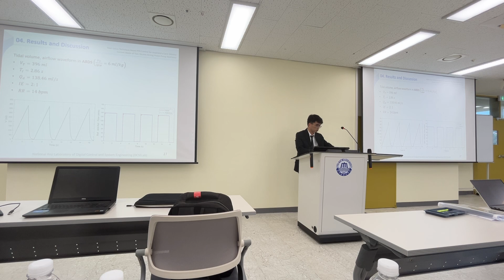You can see this flow waveform that I control. And as you mentioned before, the output of the BLDC system is not stable; the curves are all half waveforms. This will break. So the flow that I control is the average value of the airflow.